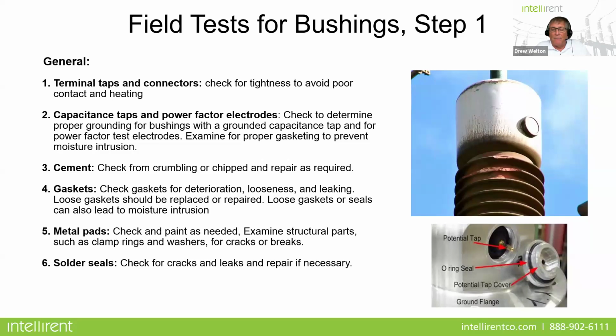But having a good eye when you're doing an inspection of bushings is really the very first step to look for potential problems. Things such as your terminal taps and connectors, you have to check for tightness to avoid poor contact and heating. Capacitance taps and power factor electrodes, you need to check to determine proper grounding for the bushings with a grounded capacitance tap. And those are the taps, of course, we use for power factor testing on the electrodes. And then examine for proper gasketing to prevent moisture intrusion. Cement, check for crumbling or chipped cement and repair it as required. Gasket deterioration is a huge problem.